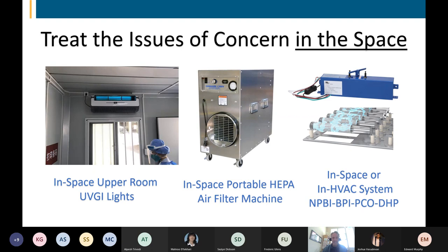As well, in the center of the slide, I show what I call in-space portable HEPA air filter machines. This is typically a box. It has a fan. It has typically a HEPA filter, which is 99.97% efficient at 0.3 micrometers. You wheel it into the space, you plug it in, you turn it on, typically on high. And if you have sized it properly for the number of air exchanges in the space that might be recommended by certain authorities or agencies, it can circulate the air in the space. And if it can, through circulation, bring those contaminants of concern back to it, so that they can come in contact with the HEPA filter inside the machine, they may be extracted from the airstream. They can be very effective as well.